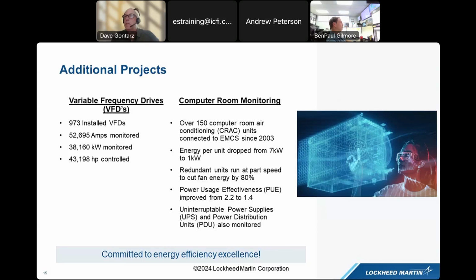We've done that with pumps and central chilled water plants and other things too. I remember once we renovated a chiller plant, and I took the operators down and said we've got to turn that second pump on. They said, come on, that doesn't make any sense. Then we actually turned two on and noted the kW versus having the one running at full speed. It's pretty cool to see that in action.